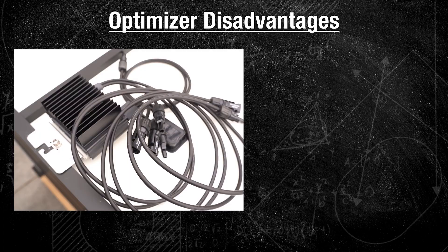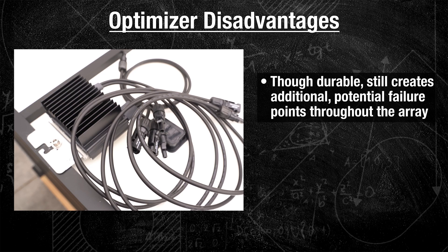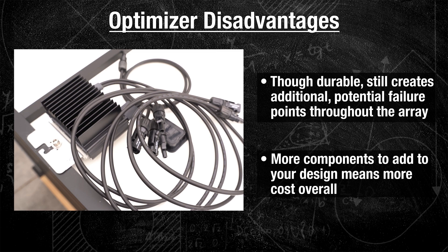It's a lot like old Christmas tree string lights — if one goes out, they all go out, and you're searching for it. In the early days of solar, it literally was that. As for disadvantages: you have one of these on every module, so it's something that could go wrong — though they're solid state and pretty bulletproof. It is more expensive since you're adding devices, but you can pencil in the return on investment with the energy benefits year over year. Smaller residential rooftop installations tend to use more of these, while larger commercial installations still often just use string inverters.